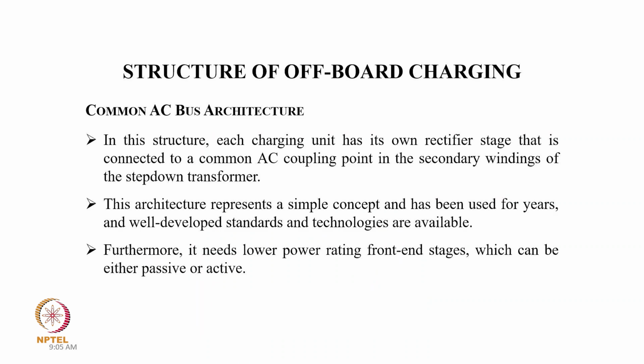Coming to the common AC bus architecture: each charging unit has its own rectifier stage connected to a common AC coupling point at the secondary winding of the step-down transformer. This architecture is a simple, well-developed concept with established standards and technology, and it requires lower power rating front-end stages, which can be either passive or active.